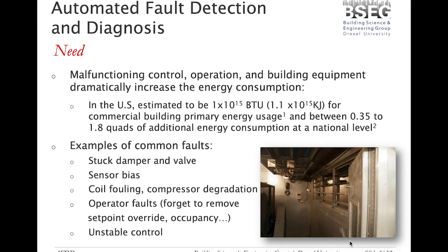So what do we mean by faults? There are common faults observable in most buildings, such as a stuck damper or stuck valve. Sensor bias is very common, especially for CO2 and humidity sensors, which are known to drift away from their manufactured accuracy. Coil fouling and compressor degradation are also unavoidable over the lifetime of a system.